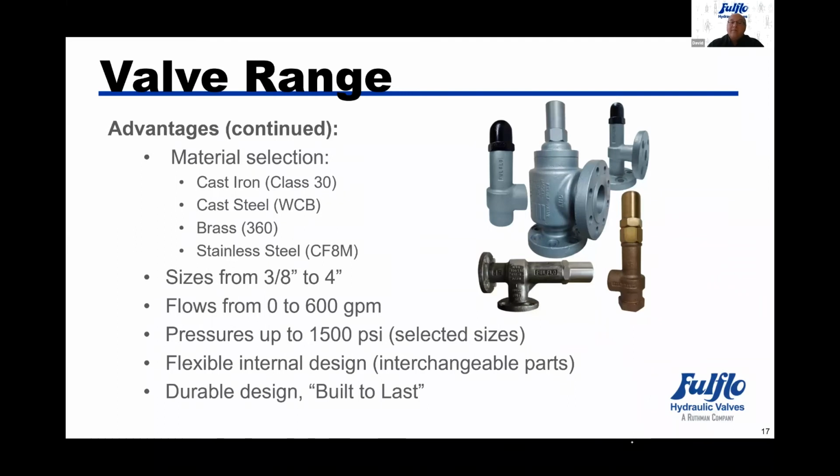The flexible internal design means we can interchange different O-rings, different pistons, different springs. So if the valve is in the field, you can take one spring out and replace it with a different spring to generate a higher pressure or a lower pressure. They're very durable. We build them to last.